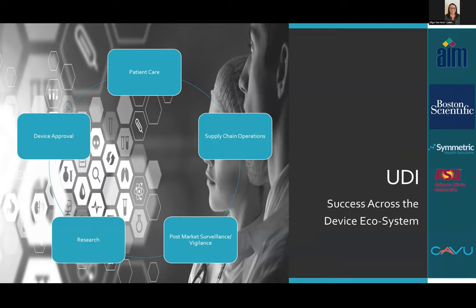Further to that, the MDR requires implant cards to be provided for all implantable devices unless they're specifically exempted. The implant card information will include, among other things, the UDI of the device. Having the UDI on the implant card will enable patients to access information regarding their implant via EUDAMED.